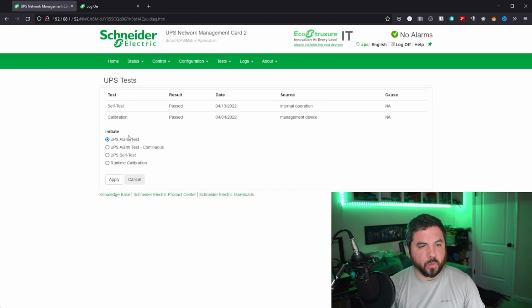There are other tests here that you can run. You can test the alarm if you want to. You can do a UPS self-test. Obviously, try this at least once and make sure you can hear it, but do it at times that it's not going to disturb anybody. If you are just running a dry test, if it is something that is a problem, you want to make sure that's loud enough to hear from inside. Another good thing to do is get a smoke detector for wherever you have this installed, so that if there's issues with the electrical and there's smoke or whatever coming off the equipment, then you have that as well.